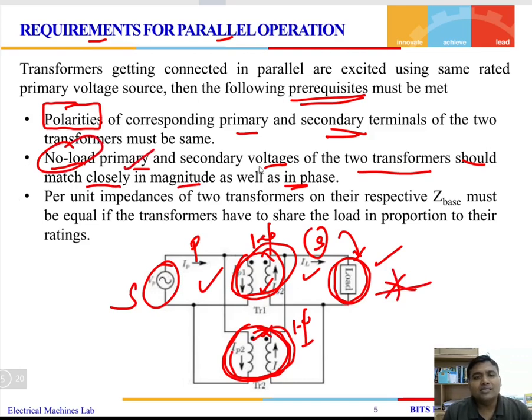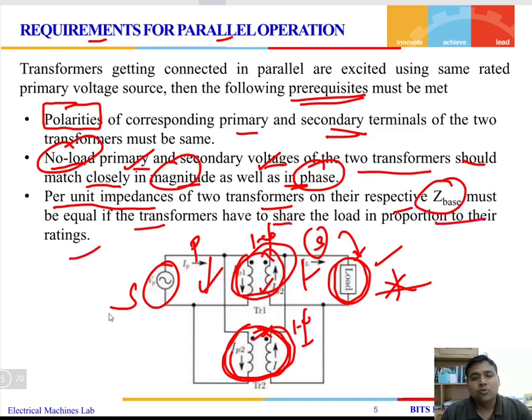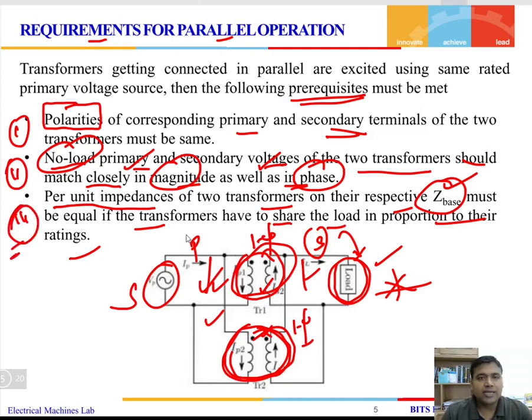Then the primary and secondary voltage. Whatever the voltage is on the primary side and secondary side, for the two transformers it should be equal in terms of magnitude as well as phase. The third condition is that the per unit impedance of the two transformers on their respective bases must be equal, because the transformers have to share the load in proportion to the rating. So if we estimate the per unit impedance of the two transformers on their own respective bases, it should be equal because they have to share the load in proportion to the rating. These three conditions, which are known as the prerequisites for parallel operation, must be satisfied so that suitable parallel operation of the transformers can be done.